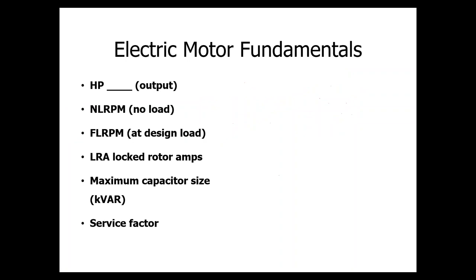Just a couple more concepts. One of them is maximum capacitor size. Remember when we were talking about power factor in an earlier module, whenever you have an induction motor or some type of magnet, your power factor is going to be lagging. Basically this angle is going to be getting larger and larger if you have more and more magnets that are messing with your electric power.